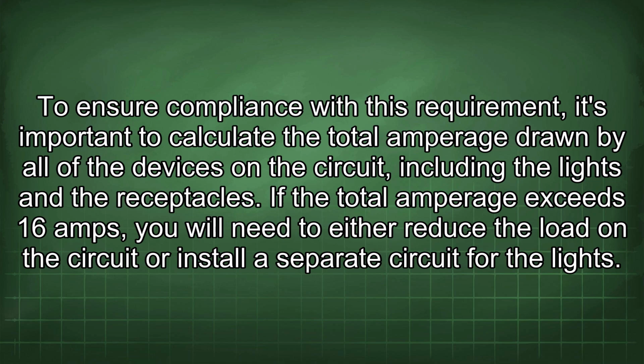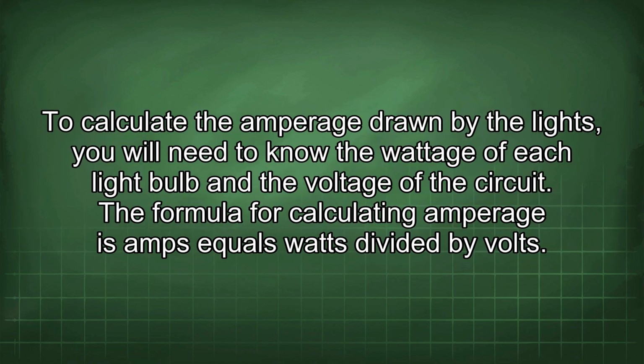If the total amperage exceeds 16 amps, you will need to either reduce the load on the circuit or install a separate circuit for the lights. To calculate the amperage drawn by the lights, you will need to know the wattage of each light bulb and the voltage of the circuit. The formula for calculating amperage is amps equals watts divided by volts.